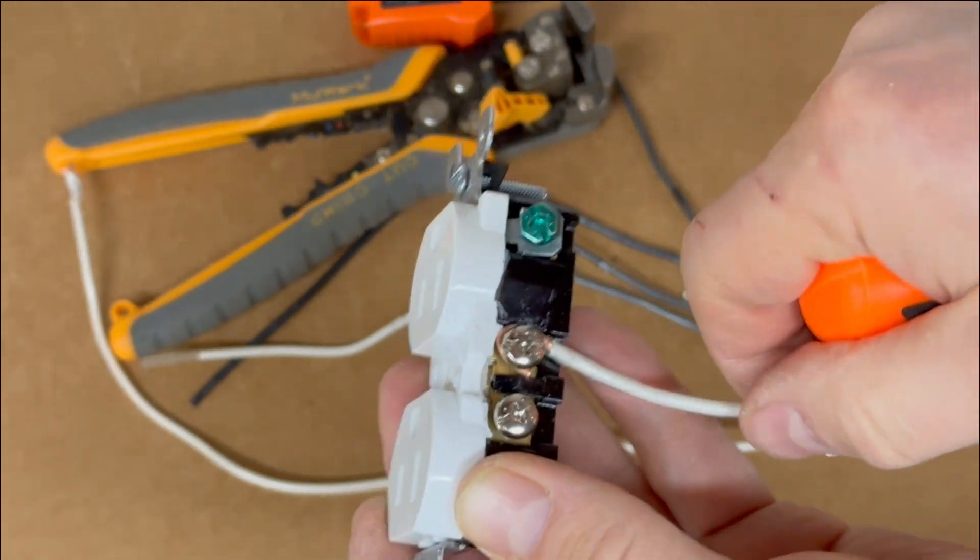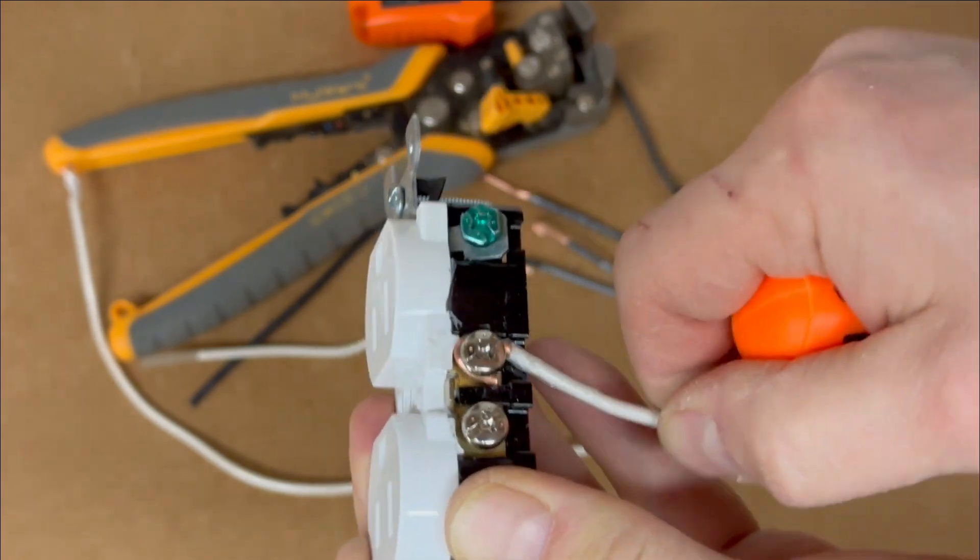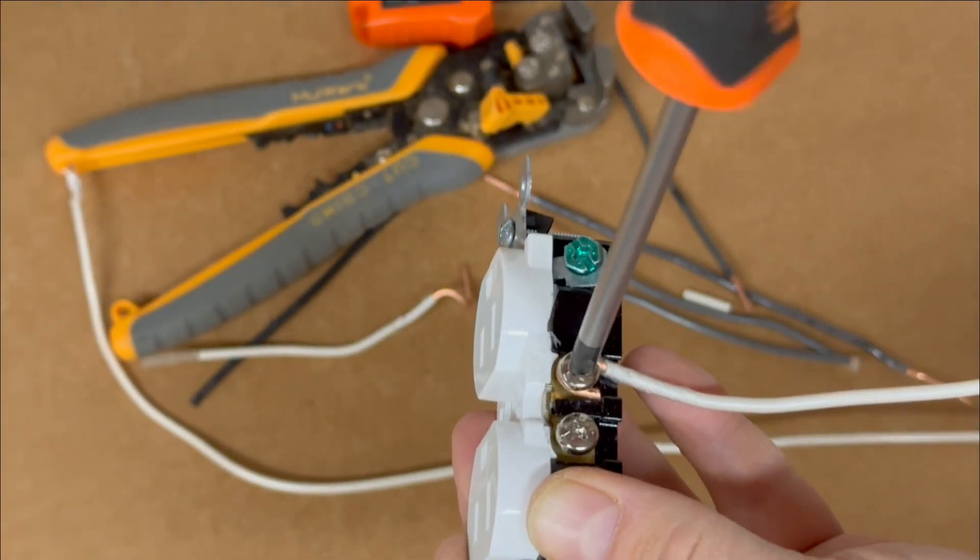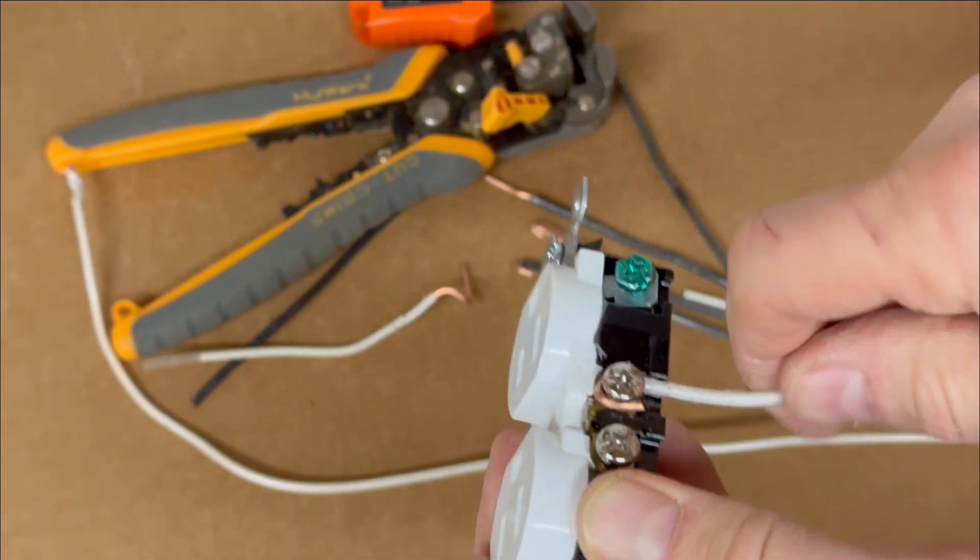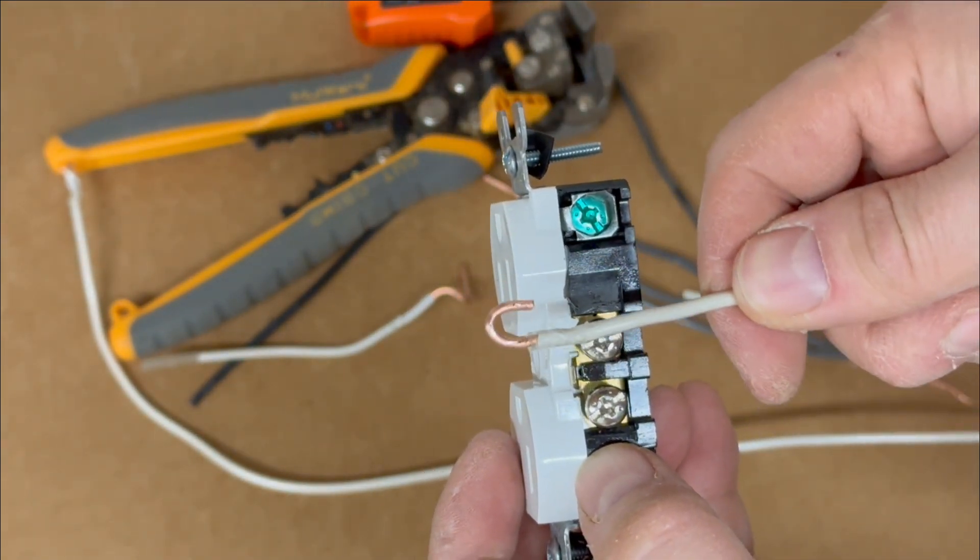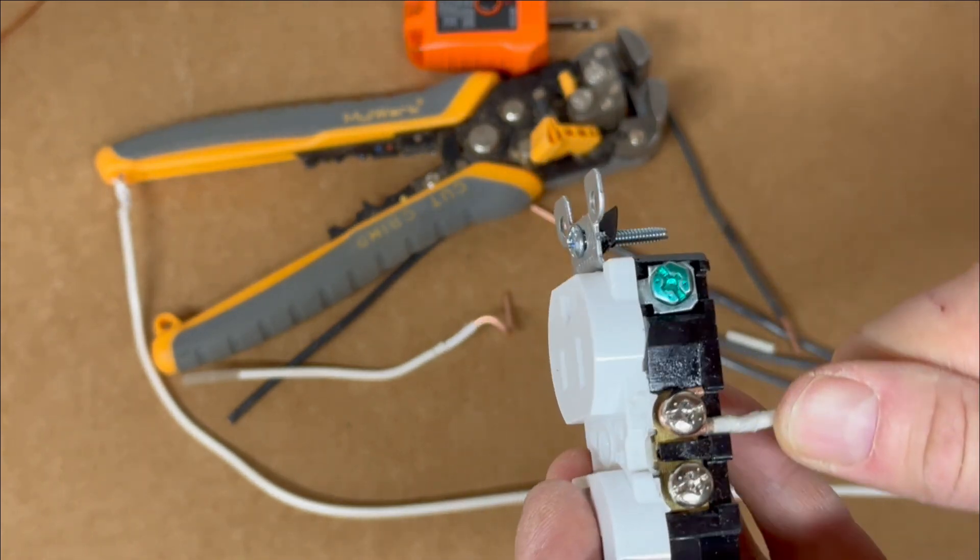When you attach your wiring in a counter-clockwise direction, the wire gets pushed away from the terminal screw. This means it won't be secured tightly in the center of the terminal screw, which could lead to a weaker connection that you don't want.